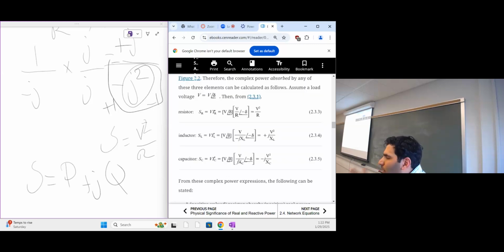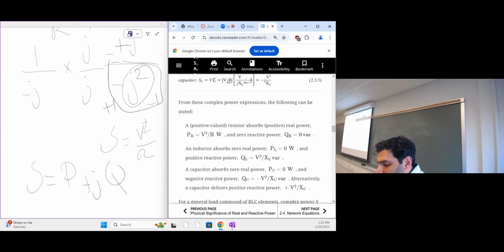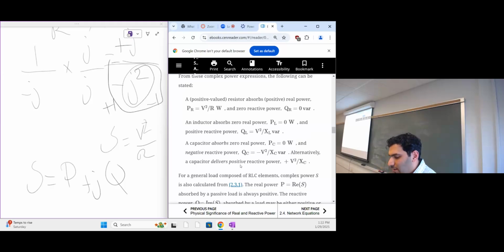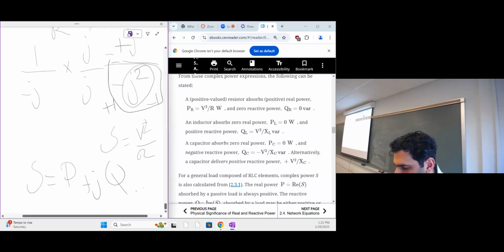So that's why now we are getting to understand why long transmission lines are bad, because they consume that reactive power and lead to a voltage drop, making the voltage drop along the long distance. To solve that, we need capacitive components to deliver us that power, which is V squared over XC.